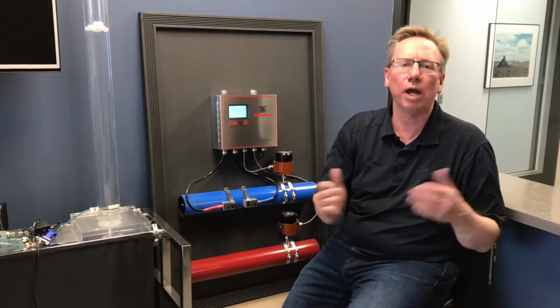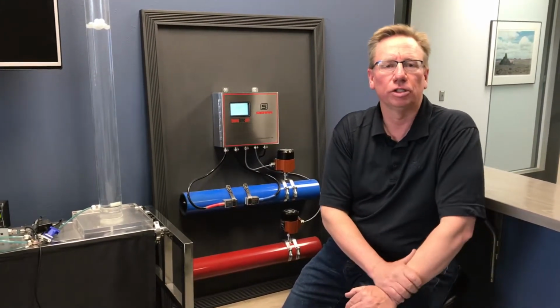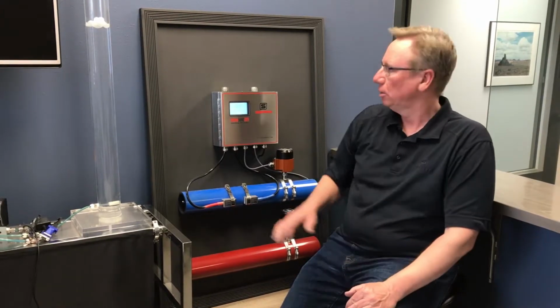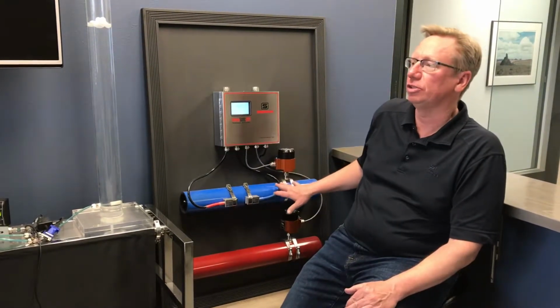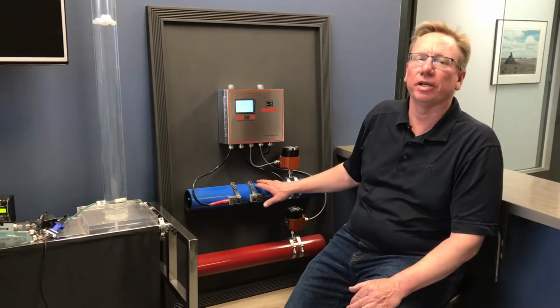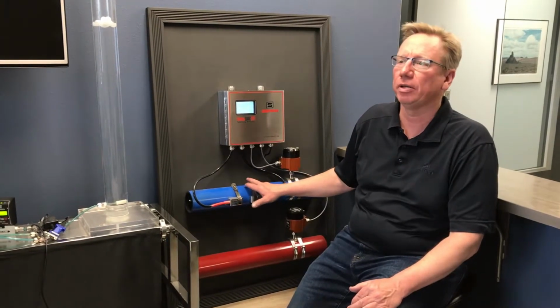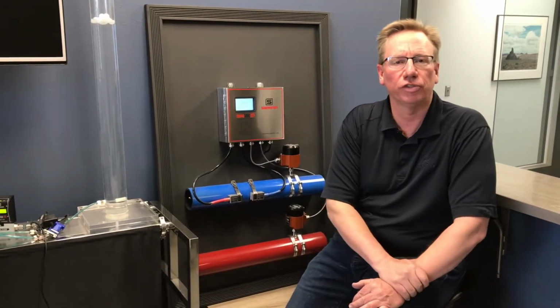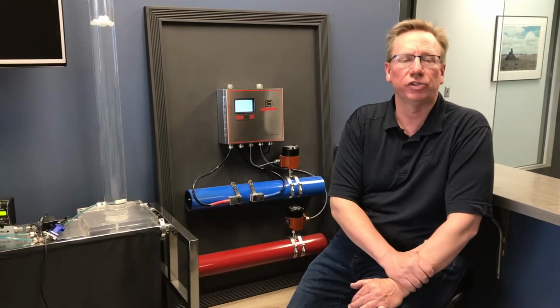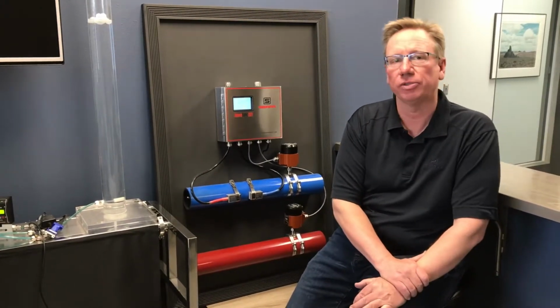Why would I be interested in making that measurement in terms of the efficiency of my building? Clamp-on ultrasonic with delta T is very critical to that, because the last thing you want is to realize that your facility, or at least half of it, has uninsulated pipes.